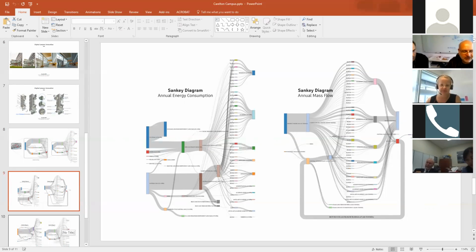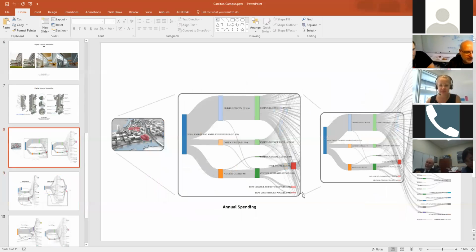Yeah, it's actually a standard library called D3 that has a Sankey diagram option. The hard part is just really collecting the data. So if you want to go back, Holly, you can see in the center there of the previous one, total energy is $12.1 million. It's probably pretty easy to find out what your total budget is. But then how it breaks down into grid electricity, 7.6 million, district water, 1.7, natural gas, 2.8. And then further to the central heating plant and what the losses are from one to the other and things like that. This is a combination of some calculated things together with the actual data, and then some estimates as well. So there is an entire research paper on this that we can send you as well.